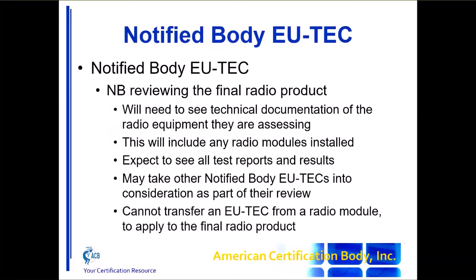So we'll go to a notified body and say, we didn't test, we've come to you instead. Because they're going to say, right, well, then you've got to either provide test results or show me how you at least are as good as the test reports, or even more. So you're going to need to provide test reports, results, or calculations at least. And you can't transfer a certificate from one thing and hope that it will apply to some other thing if it isn't listed on that certificate. We'll go over that a bit more when we talk about radio modules.